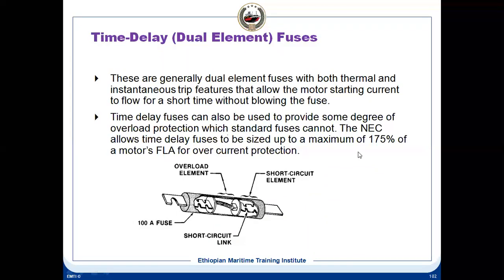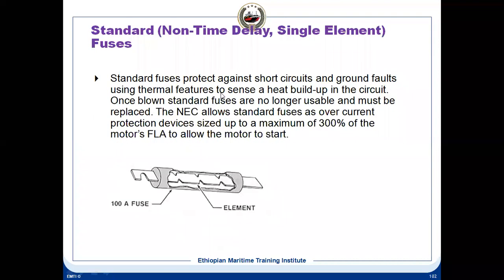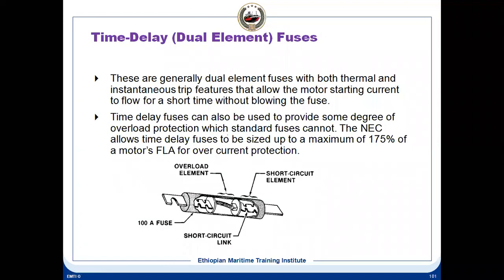But the NEC allows time delay fuses to be sized. Sizing means how much we can use. The value is up to a maximum of 175% of full load current if it is time delay fuses. If it is not time delay fuses, it can use up to 300%. Hope you understood. Non-time delay fuses, up to 300% of the full load current. If it is delay fuses, it is 175% of the full load current.